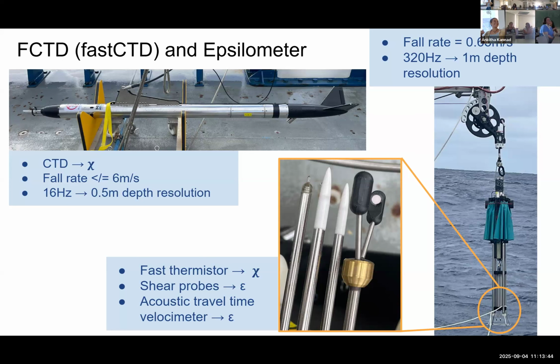Yeah, so you have two different bits of metal poking together at any given time, and the temperature differential across that creates or induces a voltage across those two metals. That signal goes into a circuit, and we measure that voltage to get the actual temperature at the tip.